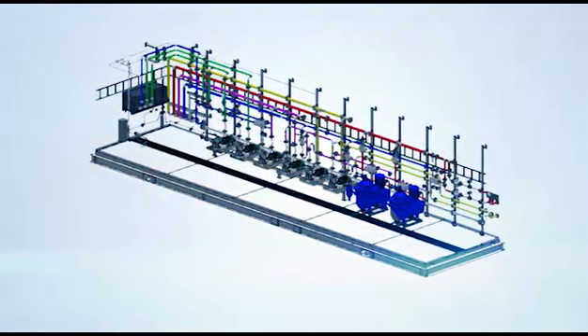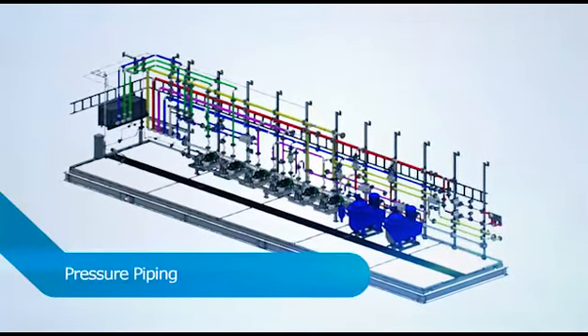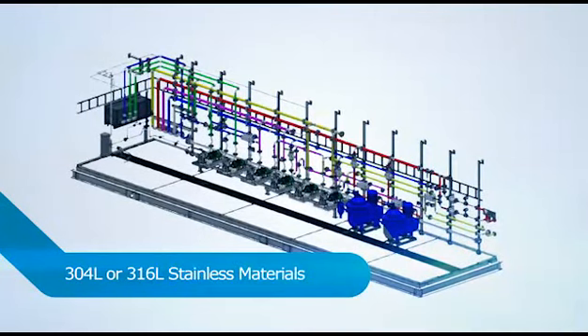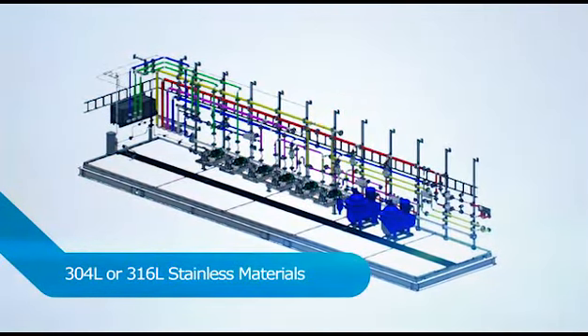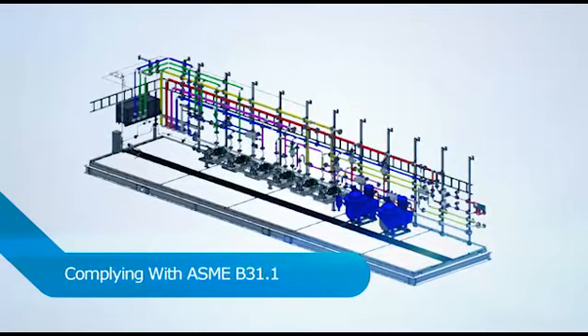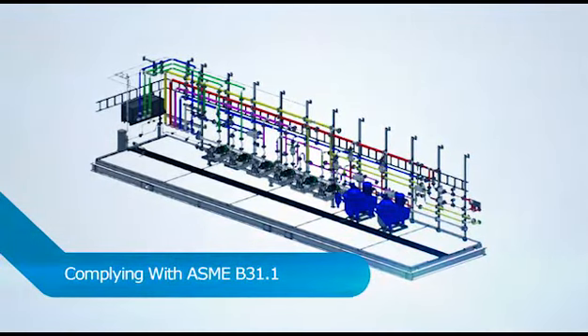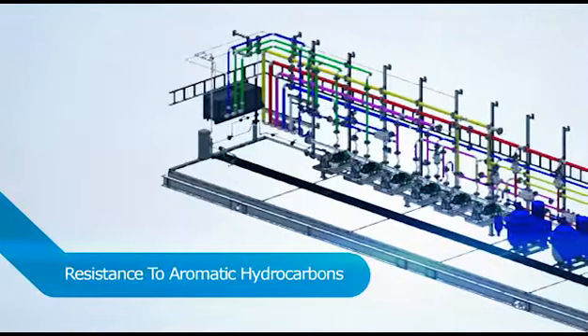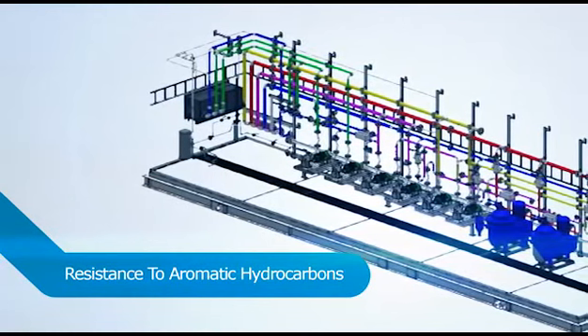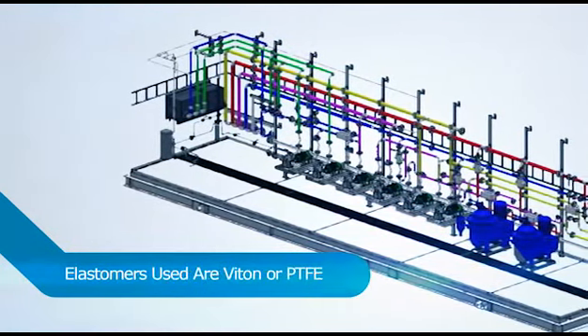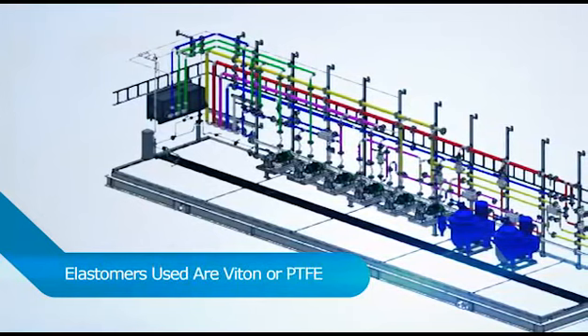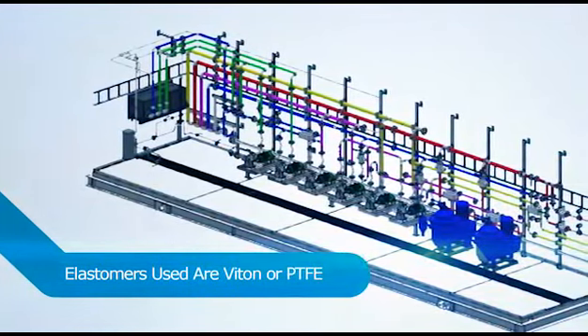Pressure piping for the fuel block and all modules is fabricated from 304L or 316L stainless steel materials, complying with ASME B31.1. To provide resistance to potential aromatic hydrocarbons, elastomers used for fuel oil service are Viton or PTFE.